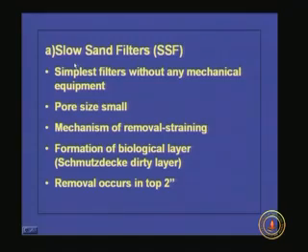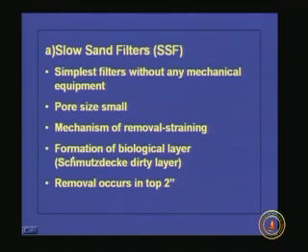So here the pore size is very, very small, and the mechanism of removal is by straining. That means the sand will be acting as a sieve, and whatever particle is coming, it will be screened or strained through the sand. So that is the mechanism of particle removal. And what will happen with respect to time, on the surface of the filter there will be a biological growth. That is known as the dirty layer. So this dirty layer is responsible for removing any dissolved solids, mainly organic matter present in the water.